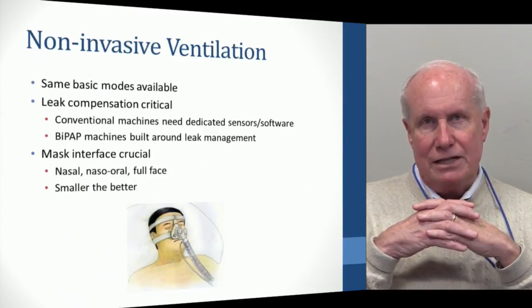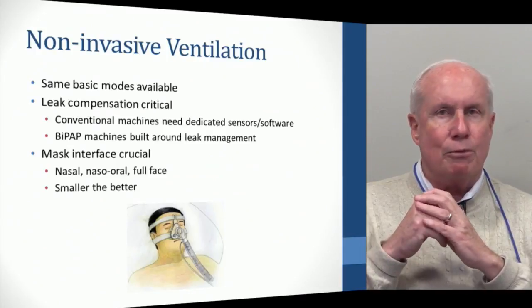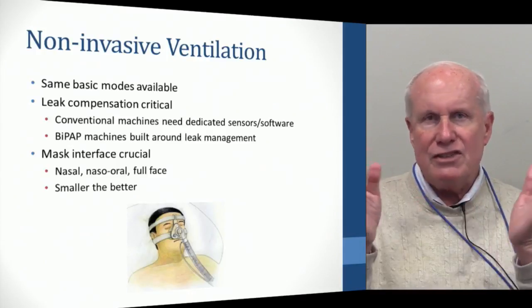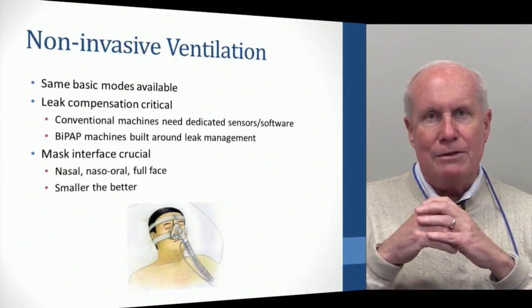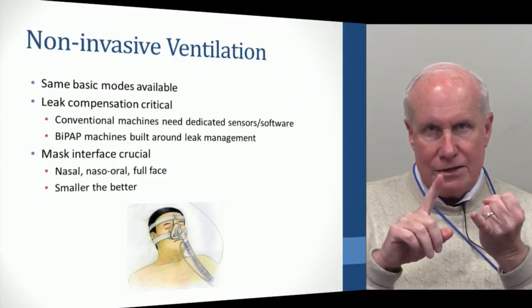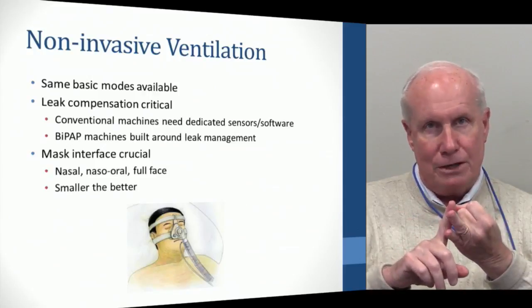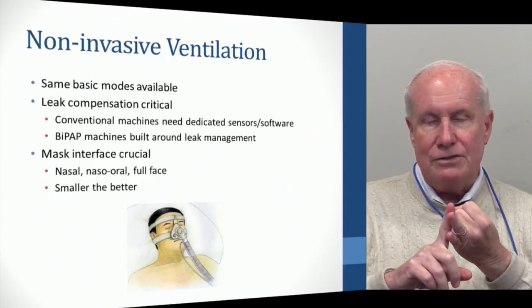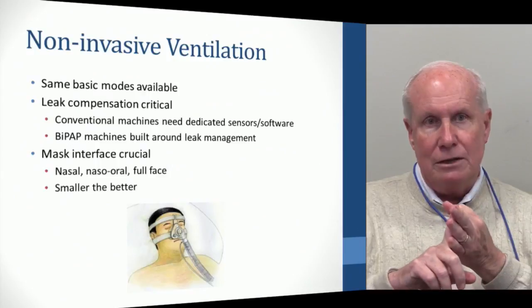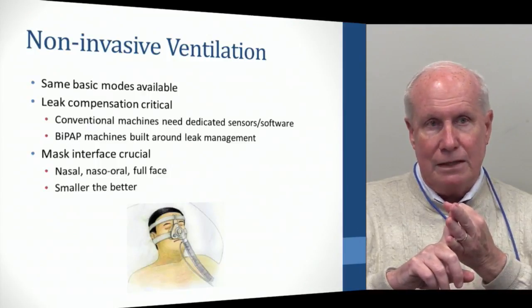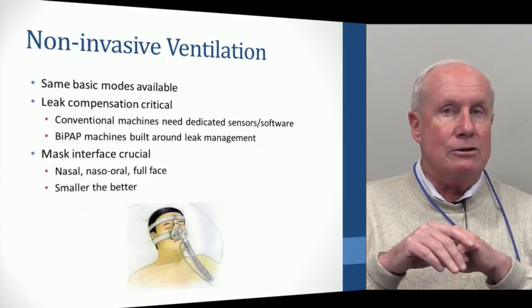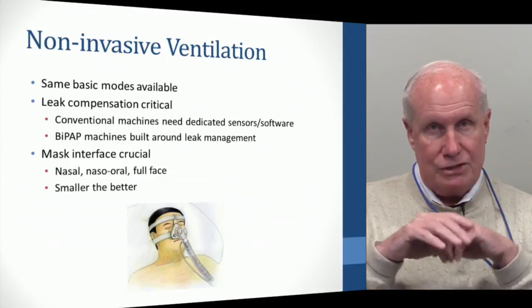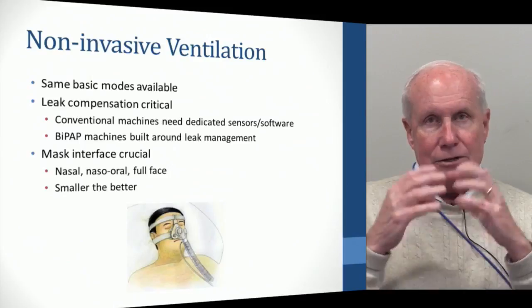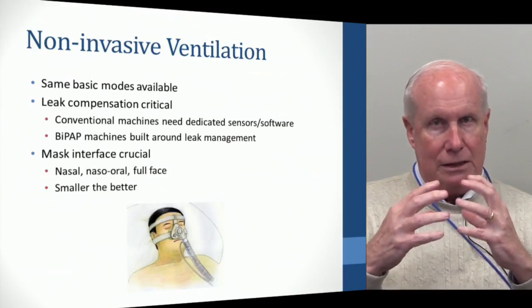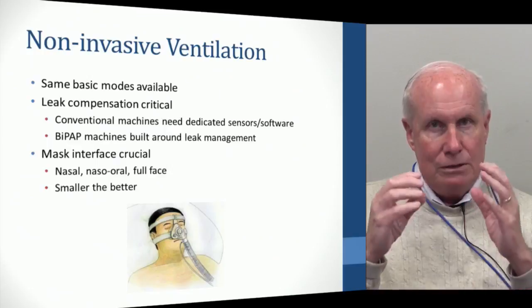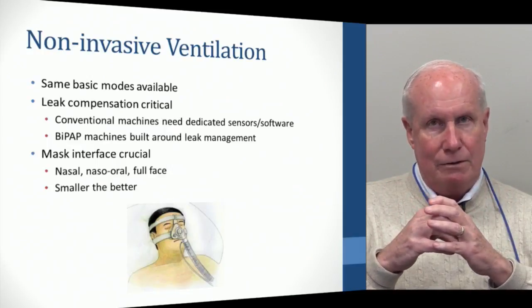Non-invasive ventilation uses the same principles I just described before. The same basic modes are available. The most common devices usually are just pressure devices. That is, they provide either pressure assist control or they provide pressure support. Some of the fancier non-invasive systems do have volume assist control, but that's not available in all of them. If you're using a conventional ventilator to drive a non-invasive system, a mask system, you have to be really careful because a mask inherently has leaks. And a conventional ventilator that we use in the ICU does not compensate for leaks very well.